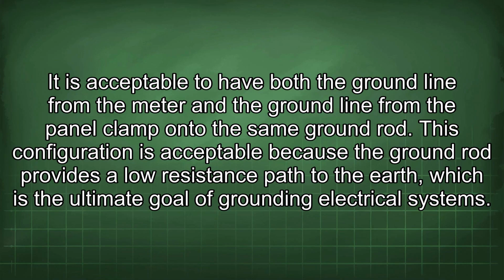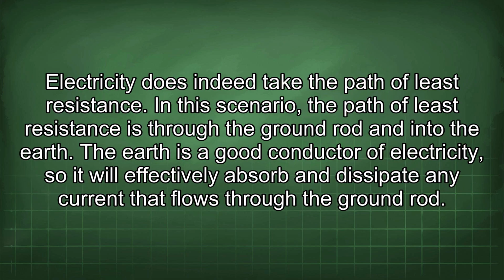It is acceptable to have both the ground line from the meter and the ground line from the panel clamp onto the same ground rod. This configuration is acceptable because the ground rod provides a low resistance path to the earth, which is the ultimate goal of grounding electrical systems. Electricity does indeed take the path of least resistance. In this scenario, the path of least resistance is through the ground rod and into the earth.